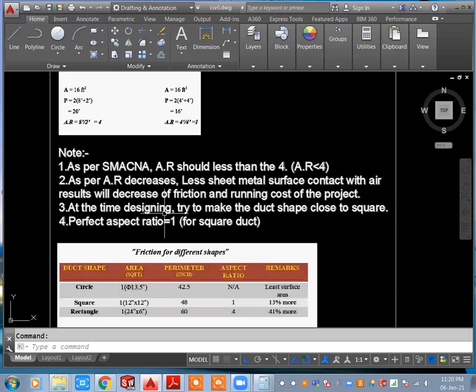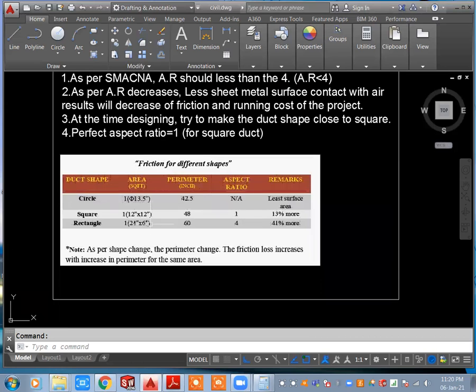At the time of designing, try to make the duct shape as close to square as possible — the perfect aspect ratio is 1 for square ducts. Looking at the comparison: a circular duct with 1 square foot area has a perimeter of 42.5 inches. A square duct (12×12 inch) has a perimeter of 48 inches and AR = 1. A rectangular duct with the same area has a higher perimeter and AR, resulting in 13% more surface than circular for square and 41% more for rectangular. As shape changes from circular to rectangular, perimeter increases, and friction loss increases with it for the same cross-section area.